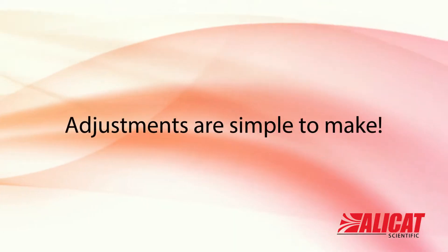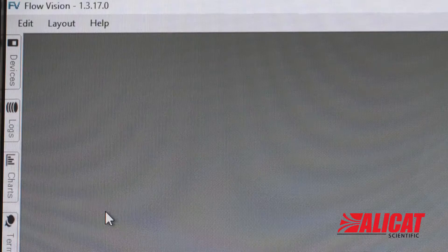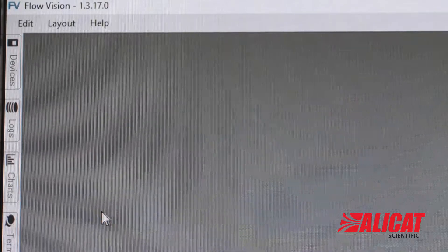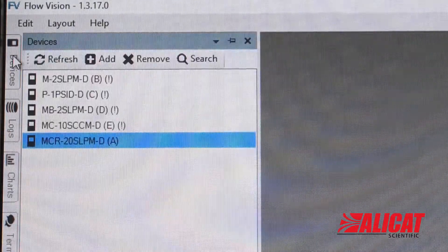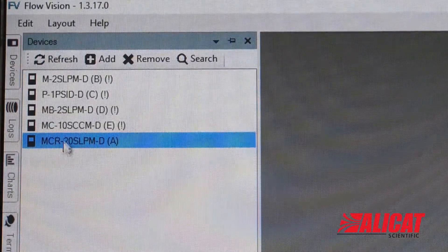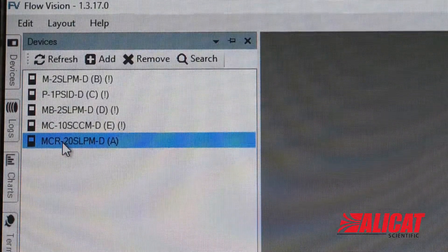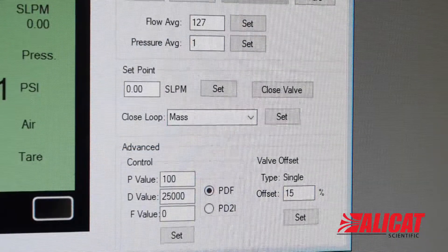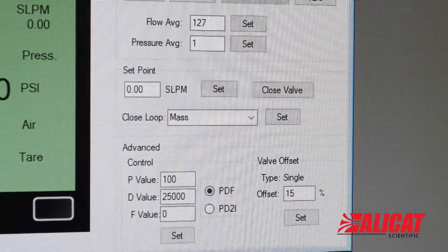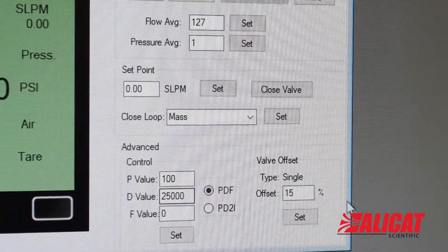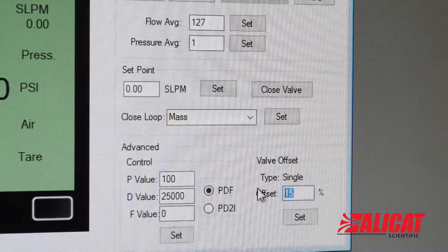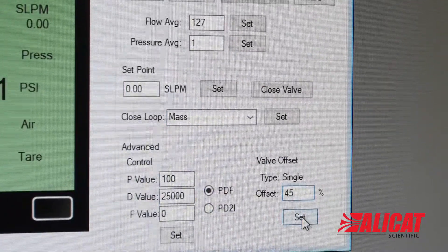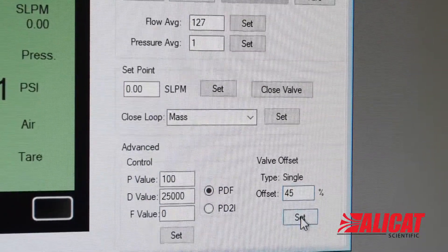Changing the valve offset value can be easy to do. Connect your mass flow controller to Alicat Flow Vision SC. Open the devices panel on Flow Vision and select your flow meter. In the bottom right corner, change your valve offset percentage to match your needs. A higher percentage means a more open valve, while a lower one means a more closed valve.